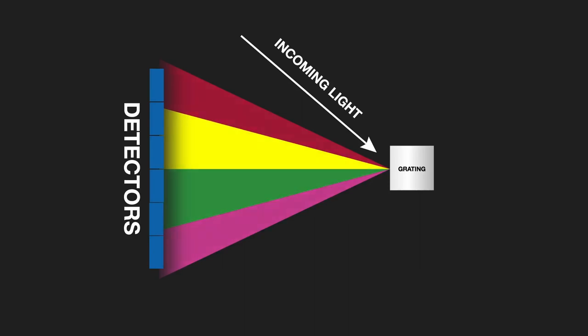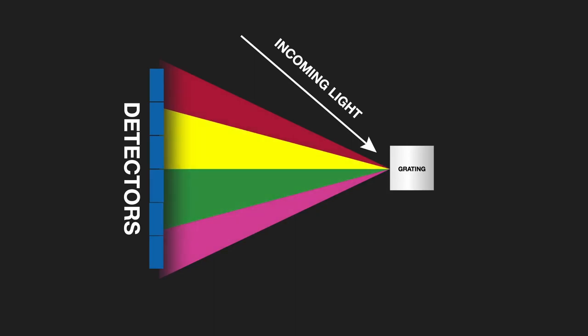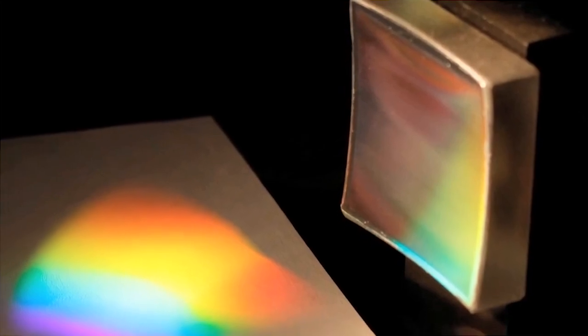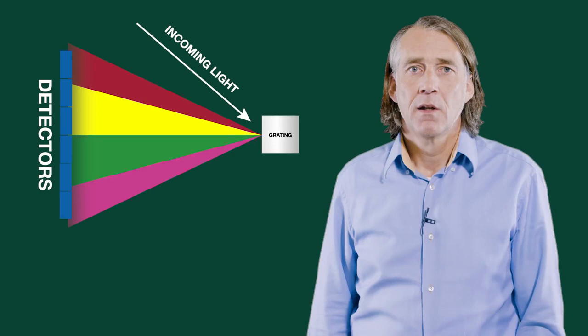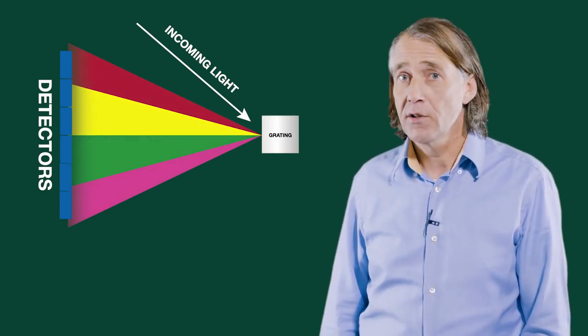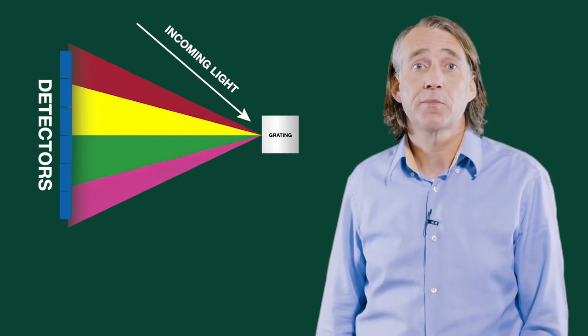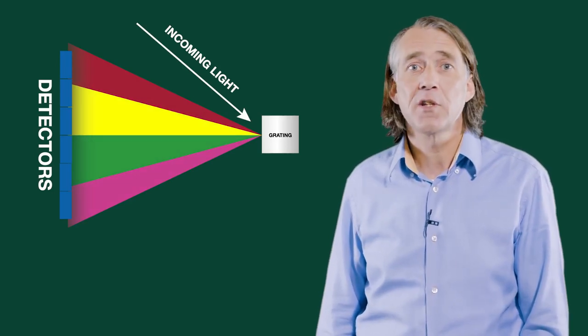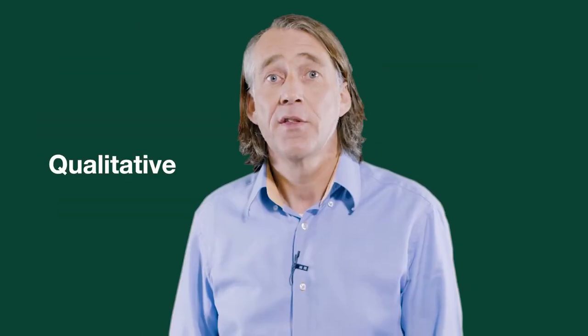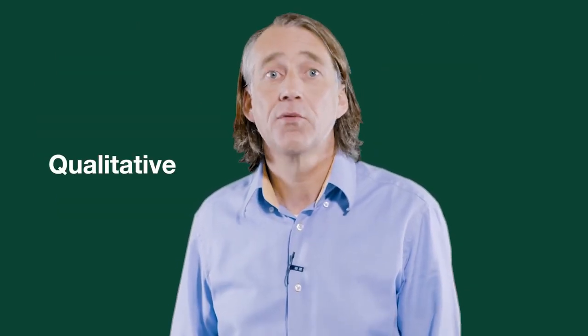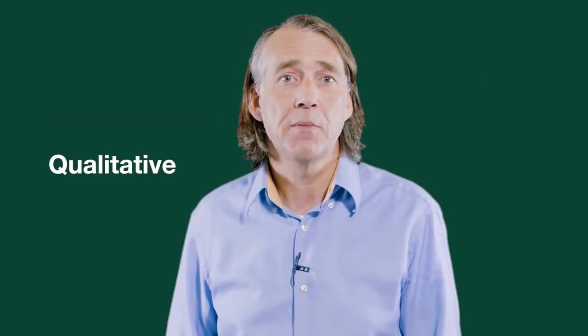The characteristic light emitted by the atoms in the sample is transferred to the optical system, where it is split into its spectral wavelengths by the high-tech grating. The grating contains up to 3600 grooves per millimeter. Next, the individual spectral line peak signals are collected by detectors and processed to generate a spectrum showing the light intensity peaks versus their wavelengths. This means that OES provides qualitative information about the sample measured.